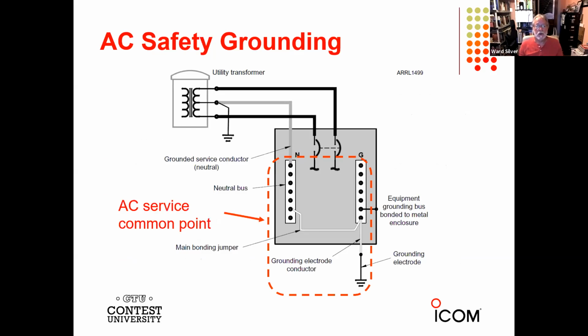Here's the AC service common point, a typical service for a house. You've got your two phases, a grounded connection at the pole, at the transformer, and then the neutral goes into your service panel. If you open up the panel and look inside, you'll see two buses. One is the neutral bus where all the white wires go. One is the ground bus that's bolted directly to the metal service box, and it has all the ground conductors, the green and bare wires.